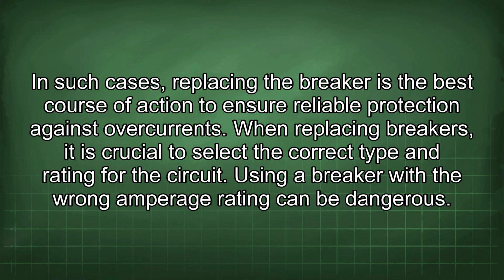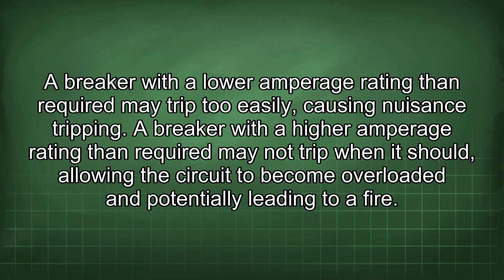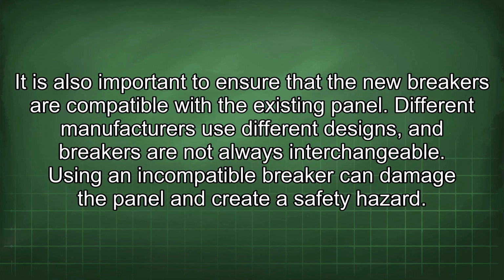When replacing breakers, it is crucial to select the correct type and rating for the circuit. Using a breaker with the wrong amperage rating can be dangerous. A breaker with a lower amperage rating than required may trip too easily, causing nuisance tripping. A breaker with a higher amperage rating than required may not trip when it should, allowing the circuit to become overloaded and potentially leading to a fire. It is also important to ensure that the new breakers are compatible with the existing panel. Different manufacturers use different designs, and breakers are not always interchangeable. Using an incompatible breaker can damage the panel and create a safety hazard.